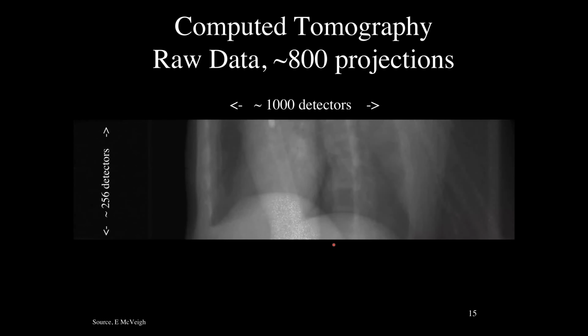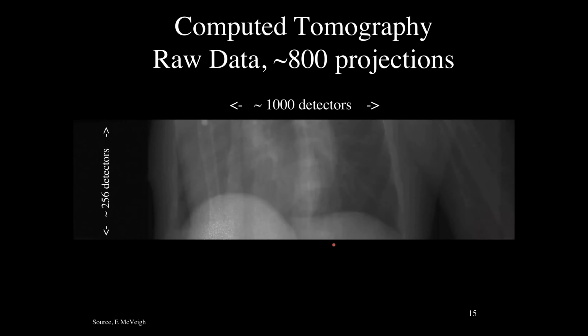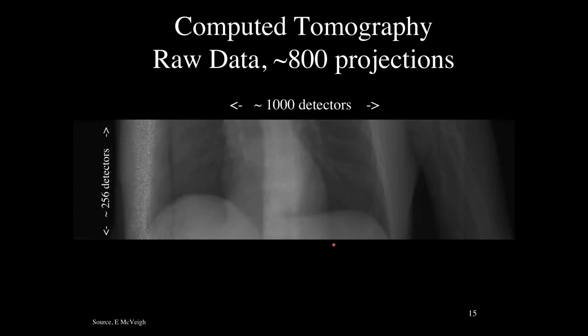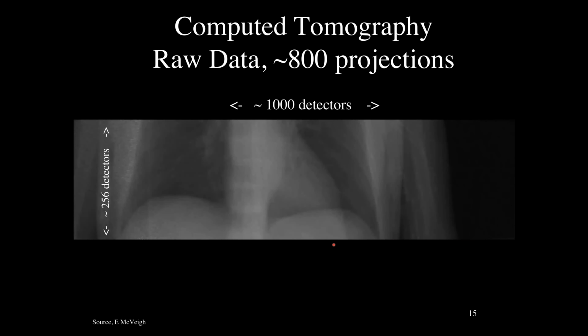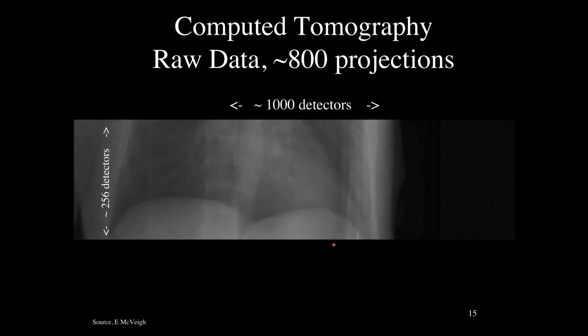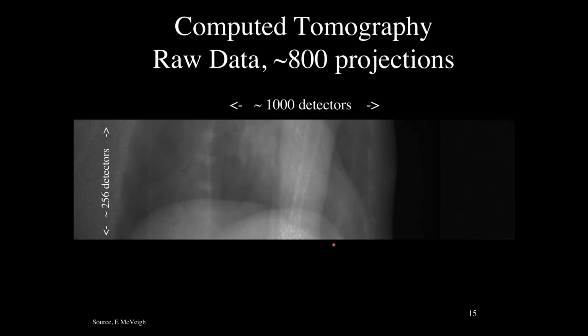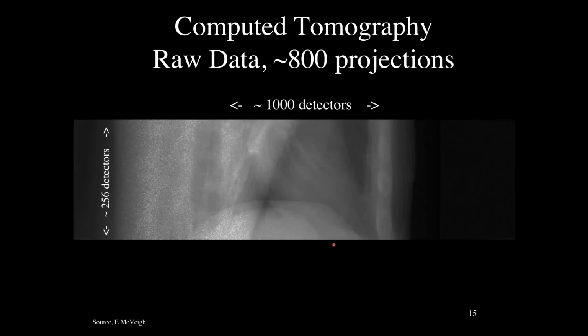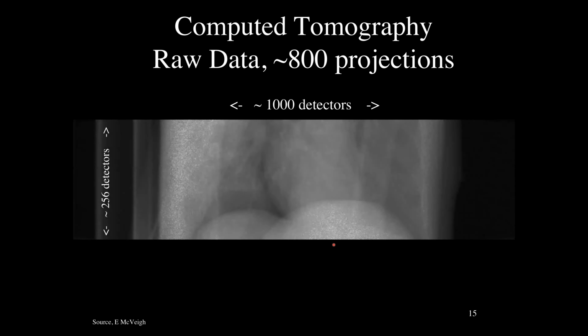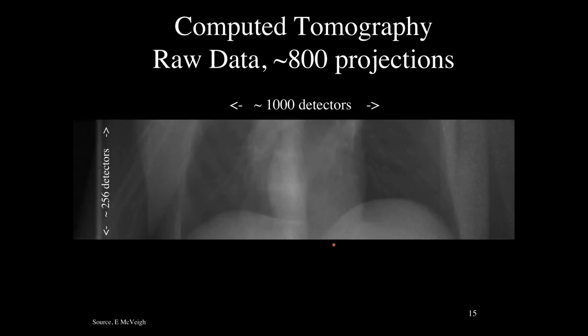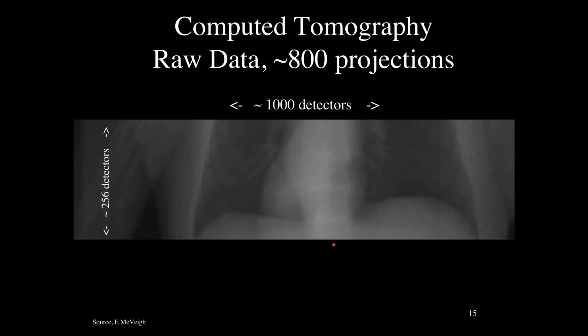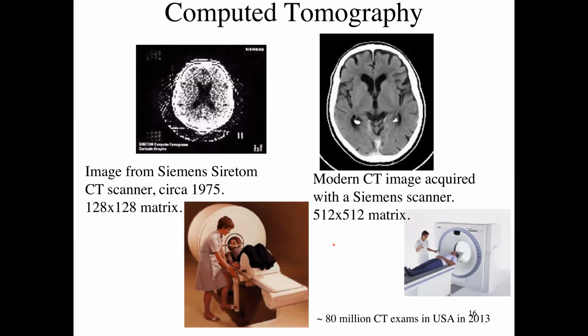It rotates around the patient 4 times a second. So about 250 milliseconds for one full rotation around the patient. And you're taking approximately 1,000 views for each rotation. So that's the speed of the data coming out of the thing, which sounds like a lot. It is a lot. It was challenging for companies to do that.